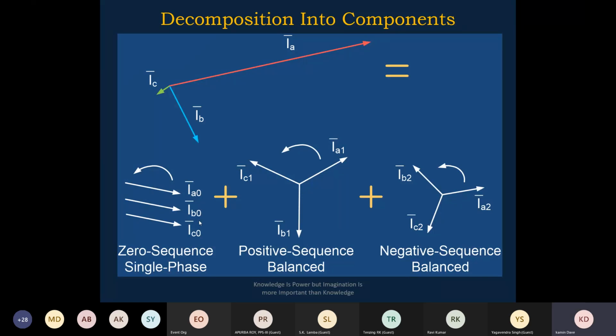Or if it is 100% phase reversal, like in a motor, sometimes during commissioning or cable termination, the mistake has been done in many places. That is called 100% phase reversal. So the negative sequence current is 100%, almost 98% of the current is negative sequence current in that case. So any unbalanced phasor is equal to positive sequence plus negative sequence plus zero sequence component. Based on these components, we can identify whether the condition is balanced or unbalanced.